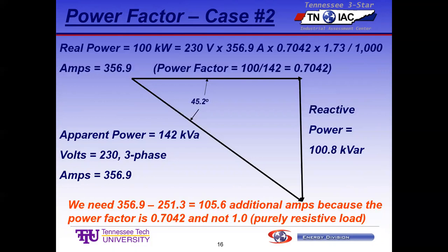So look at the reactive power. And you get this from, usually the bill will tell you the power. If you're doing a whole plant, the bill will tell you the power factor. Or I've got a 3-phase power meter. I can clip on a motor, and that meter will tell me what the power factor is on the motor. I just measure it if I want it on a particular load. Or you can put your meter next to the plant meter, or you can tie into the utility and see what they see. And you go, oh my God, they're going to kill me this month. You can see it coming.